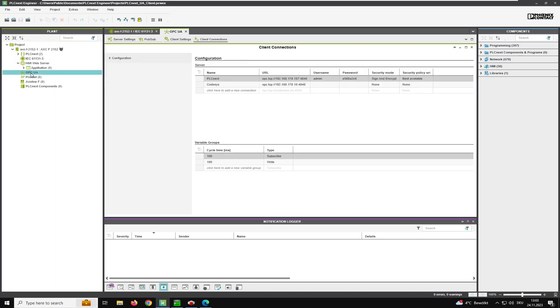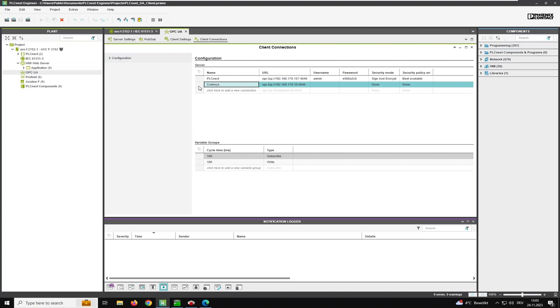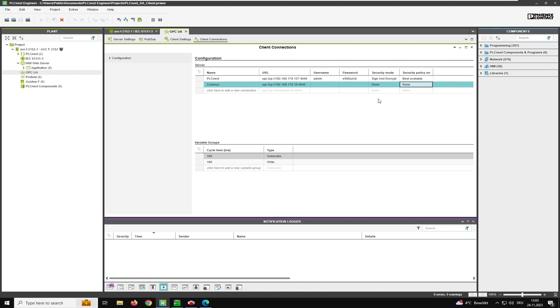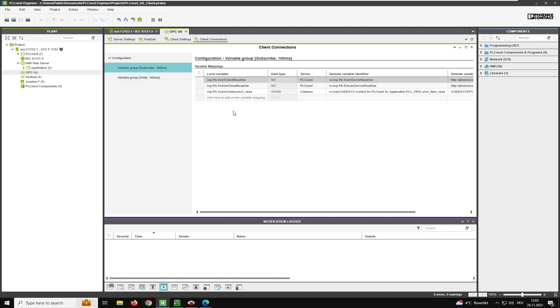Open the OPC UA node and jump into the client connection settings. I've already added an additional server to the server configuration — the name is Codesys and it has the configured IP address. As we activated the possibility for anonymous login, you can disable the security mode and security policy URI. If you choose a security option, you might have to copy certificates to the trust store of the PLCnext, as explained in the previous video. Now you can add to the subscribe and write group the items of Codesys.